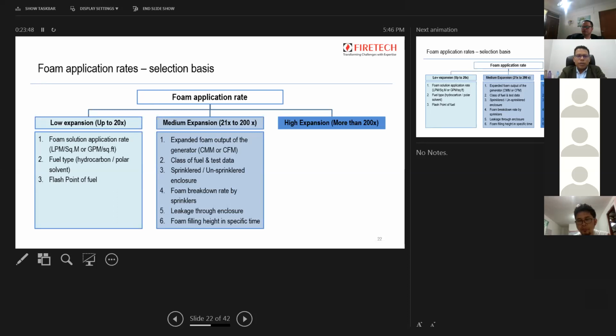When it comes to medium expansion foam systems, the foam is calculated in terms of the generator output, that is in cubic meter per minute or cubic feet per minute. Then the second consideration is the class of the fuel and the test data related to the fire. Third is whether the enclosed building or enclosure is provided with sprinklers or is an unsprinklered building. Fourth, what is the foam breakdown rate by the sprinklers, which is estimated by a number of tests. Fifth is the leakage through the enclosure, so how good is the integrity of the enclosure in which the foam is to be put. In case there is some leakage due to openings or voids, then the leakage factor is to be taken into consideration. And the most important is in how much time a specific height of foam should be built within the enclosure.